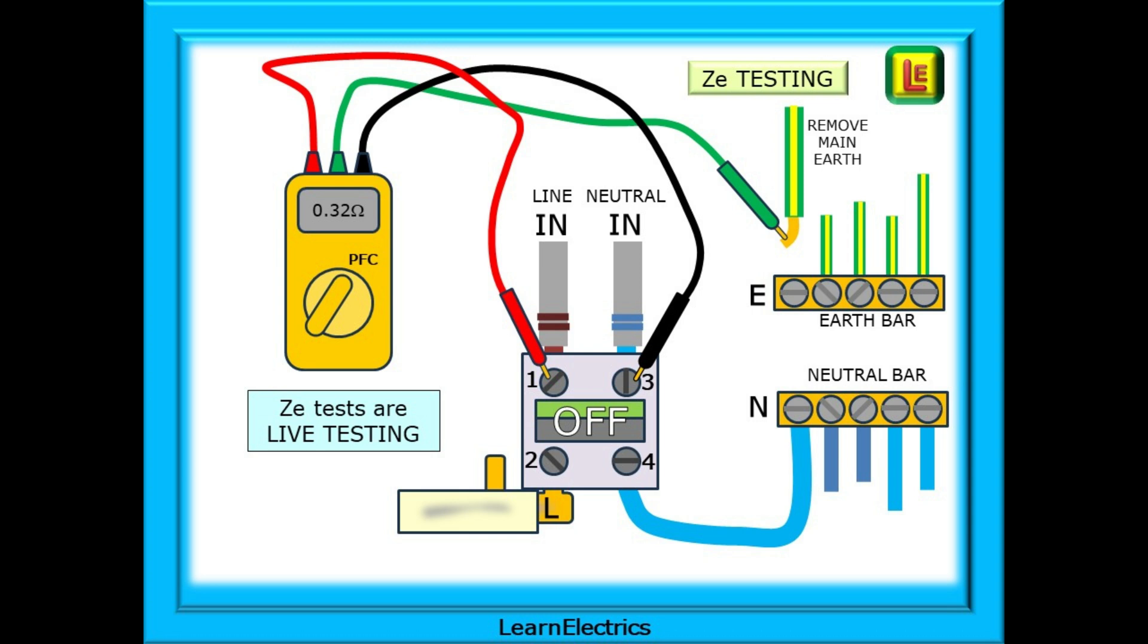This drawing shows a ZE test with a three-wire tester. Some testers only require two leads, the line and the earth. The main earth conductor is removed to eliminate parallel paths affecting the readings. The installation is turned off but this is still a live test so take suitable precautions for your safety.